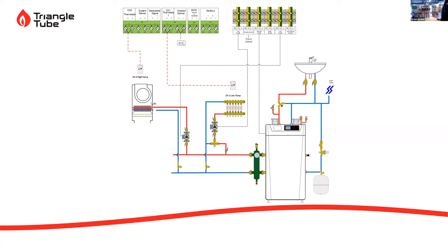So you get an accessory box that comes with it. The floor boiler is in the accessory box. This one was for a wall boiler. But in your accessory box, you're going to get a little brass bleeder key. It has a little square end on it, and that's used for the bleeder ports on the unused low loss header side. But on the bottom of the boiler where all our piping is, there are bleeder valves. So if you want to completely drain this boiler down and get all the water out of it for service purposes, or if you're winterizing it, there are bleeders on the bottom points of this boiler. We do have a drain down point at the lowest point in the boiler to get that water out.